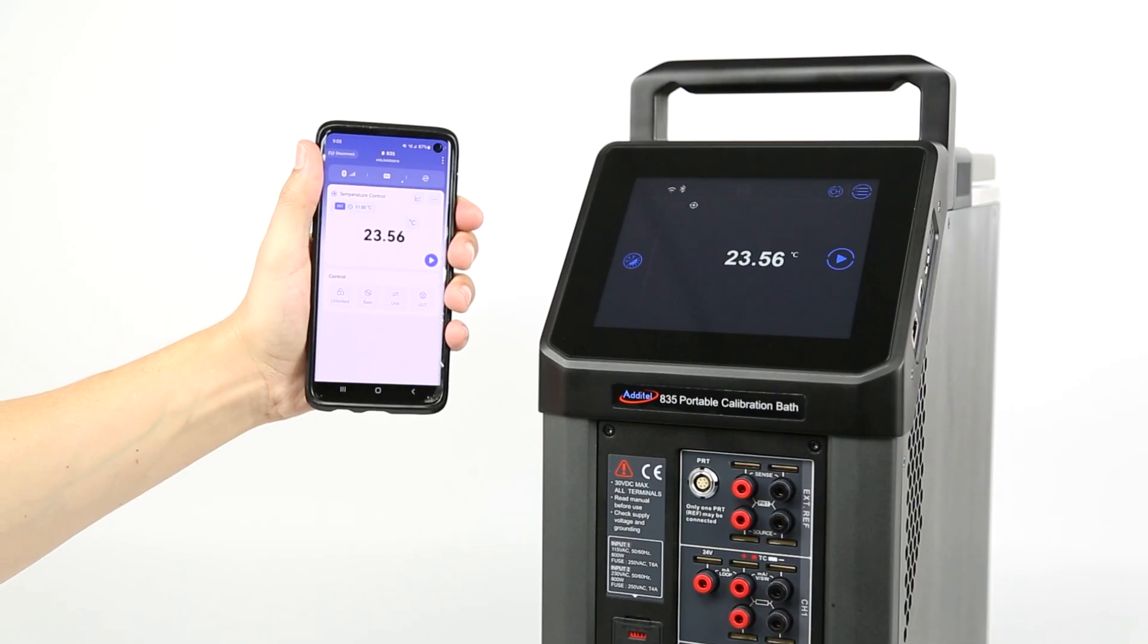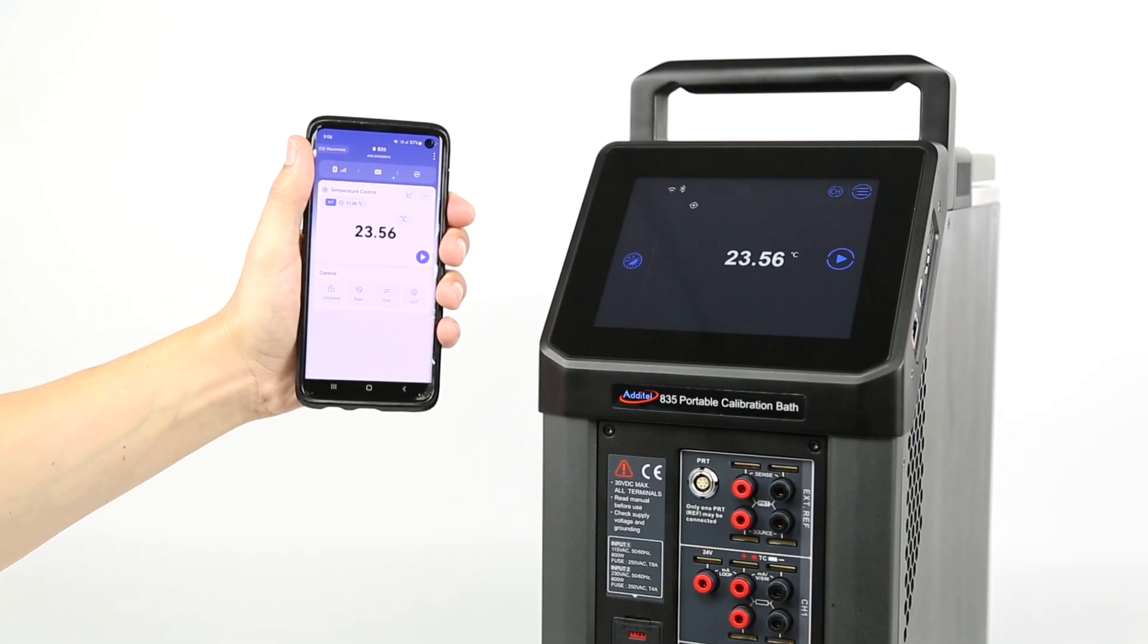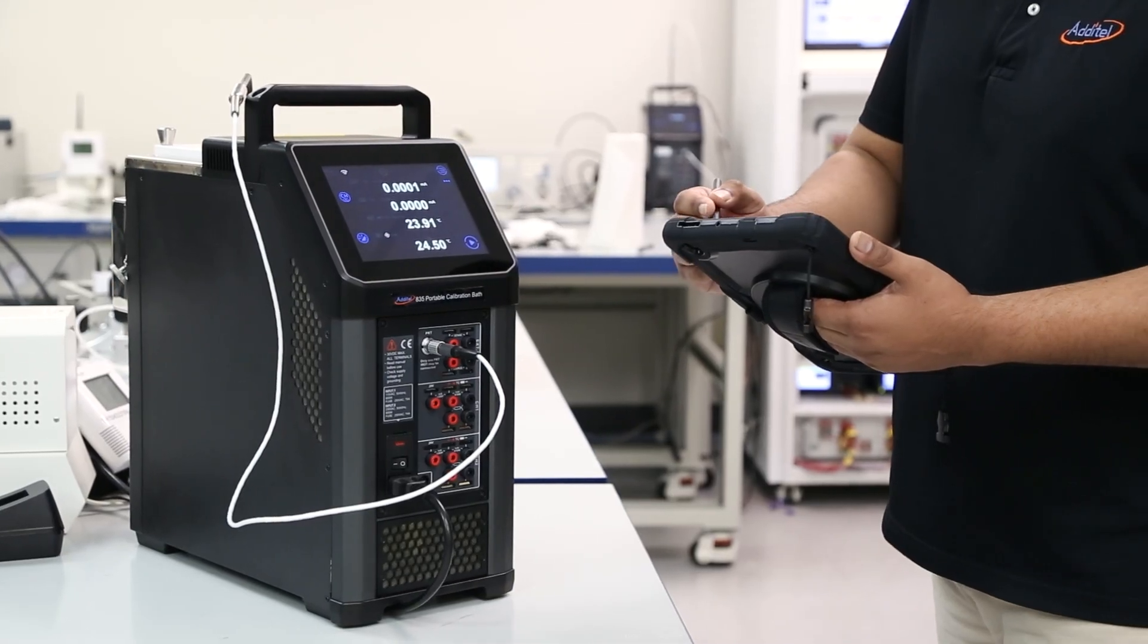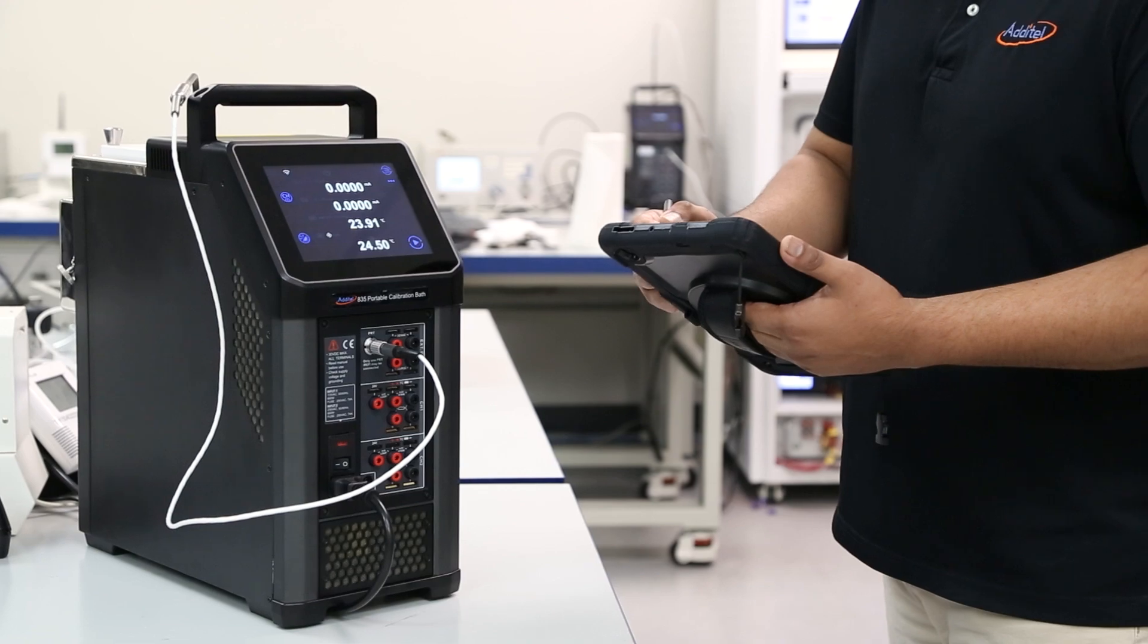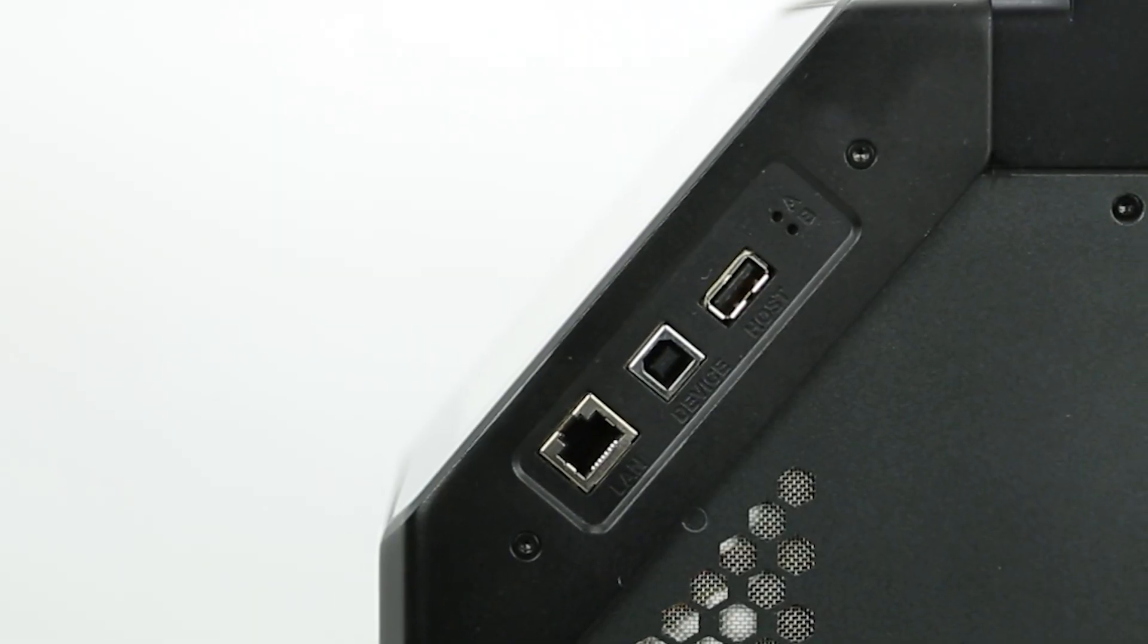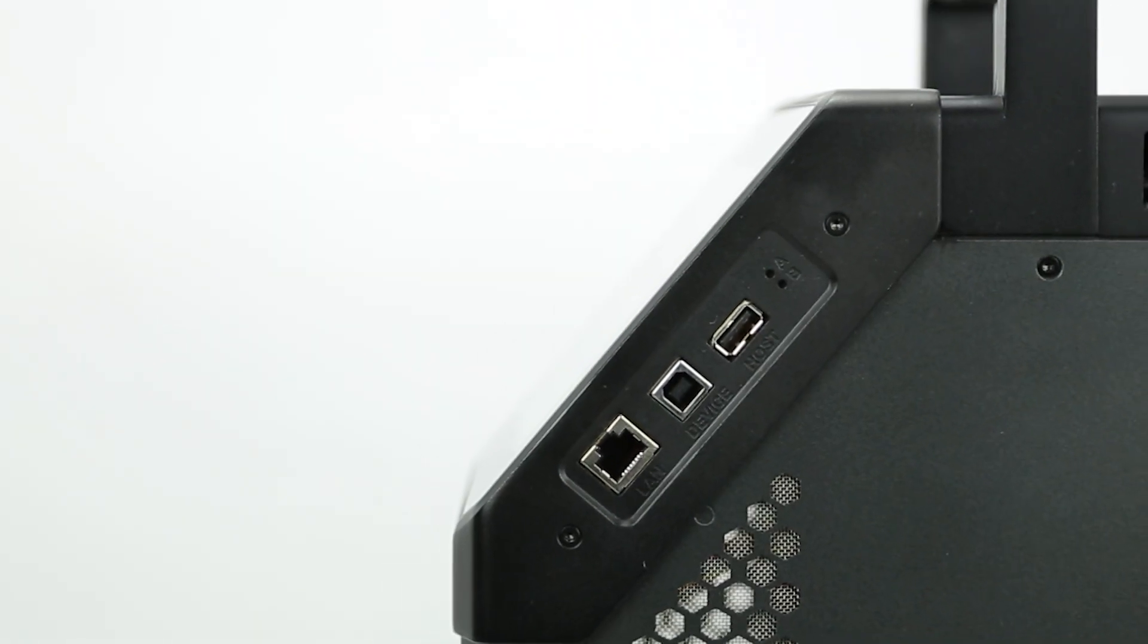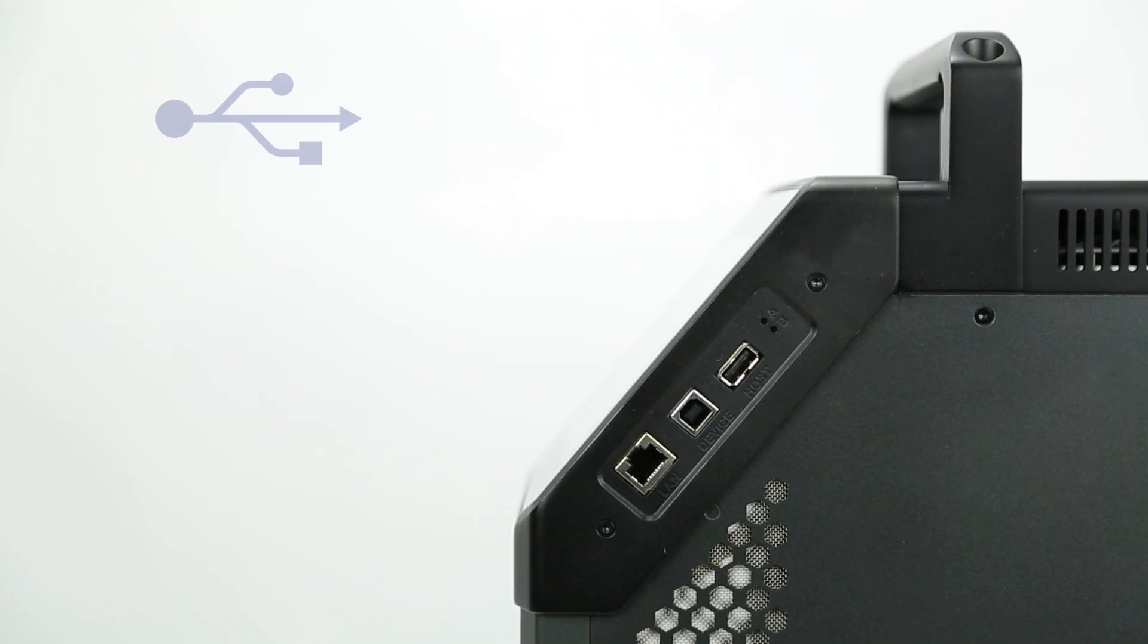Additionally, the bath can be controlled and monitored using Bluetooth or Wi-Fi, enabling technicians to multitask while still supervising the current calibration. Calibration data can then be exported to lab software through various communication channels, including USB, Ethernet, and Wi-Fi connections.